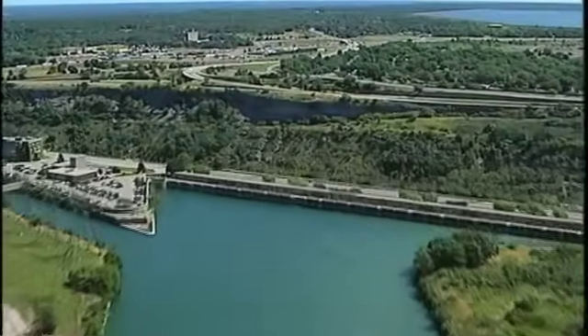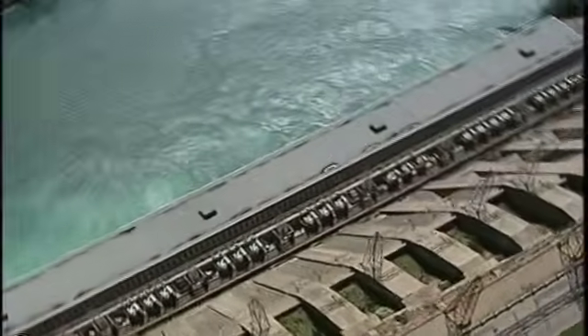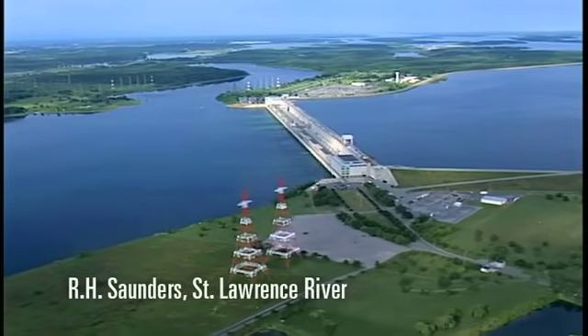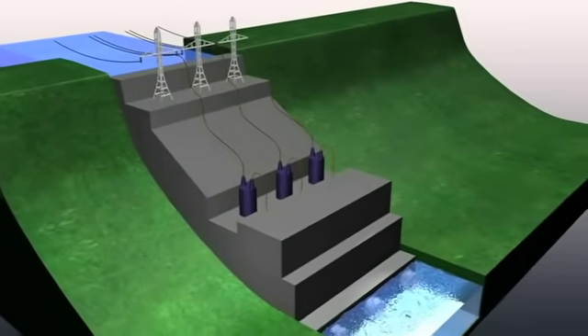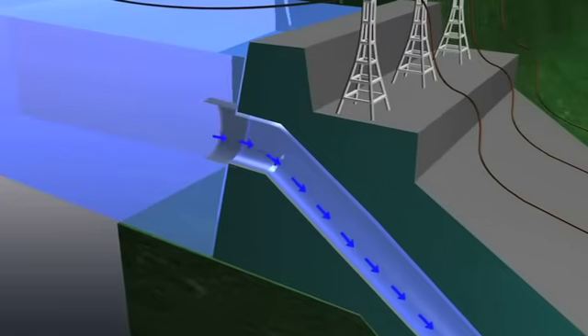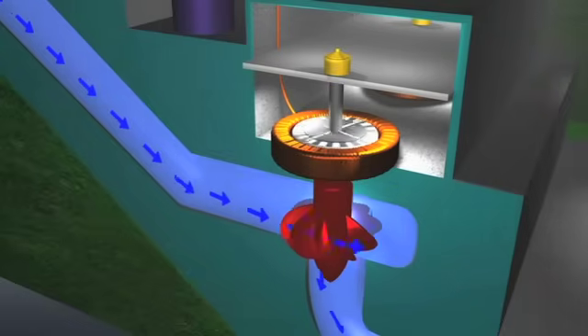Most hydroelectric stations use either water diverted around the natural drop of a river, such as a waterfall or rapids, or a dam is built across a river to raise the water level and provide the drop needed to create a driving force. Water at the higher level is collected in the forebay. It flows through the plant intake into a pipe called a penstock, which carries it down to a turbine water wheel at the lower water level. The water pressure increases as it flows down the penstock, and it is this pressure and flow that drives the turbine connected to the generator.